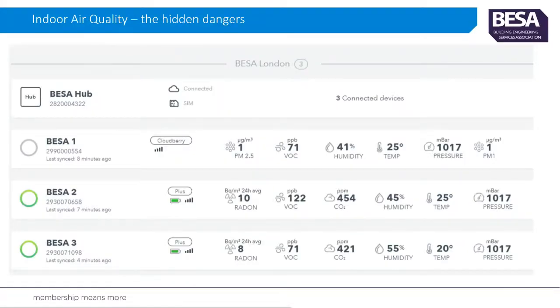So what have we been doing at the BESA Group? This is a snapshot here of readings in our London office. So we installed Airthings IAQ monitors in our offices in London and Penrith to ensure our own staff were safe by maintaining good ventilation levels and keeping the crucial CO2 level down, really crucially. We did see in London that the CO2 level was actually quite low throughout the day, which was very good. And last week we actually had a technical committee meeting, and we had more members turn up for the face-to-face meeting than we expected. But I was able to monitor in real time that the CO2 level in the meeting room didn't rise to alarming levels, which was very, very useful.